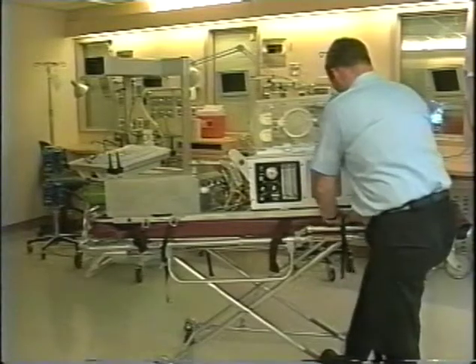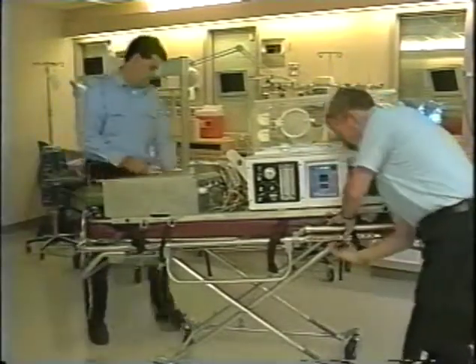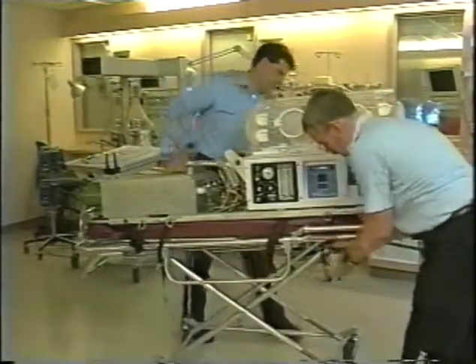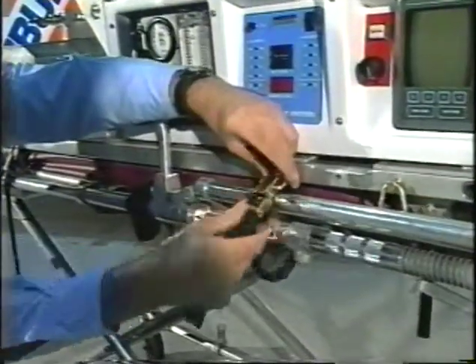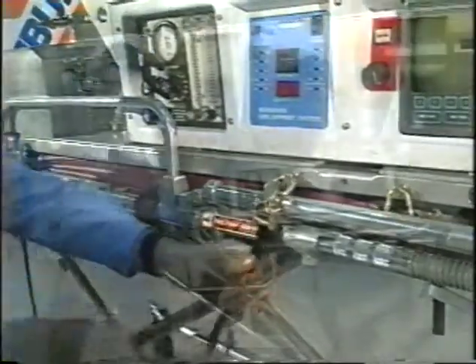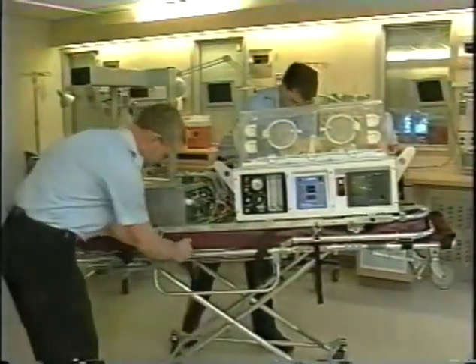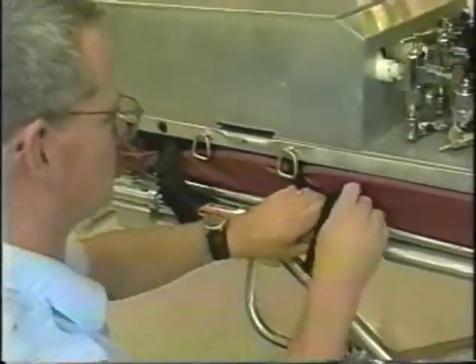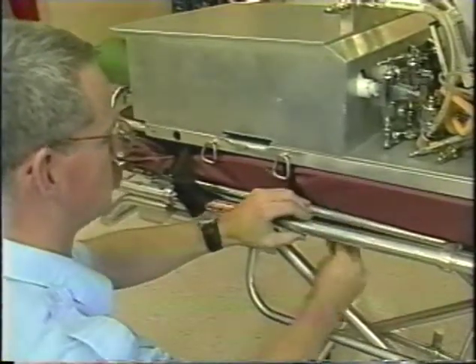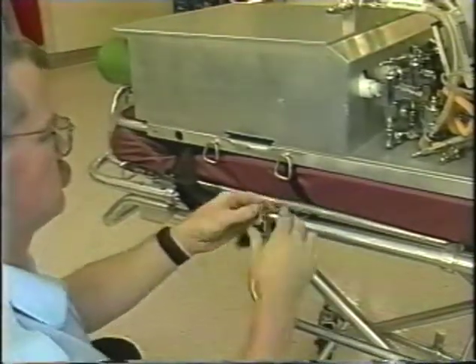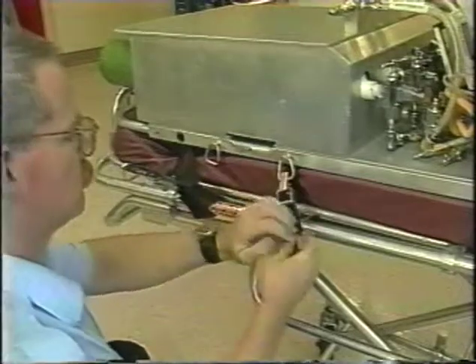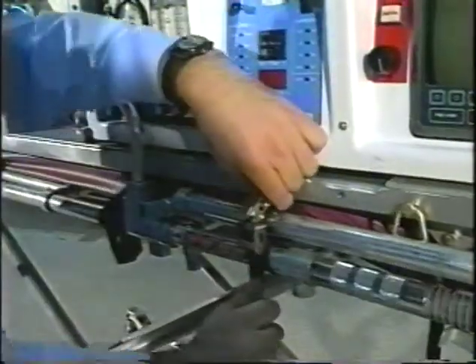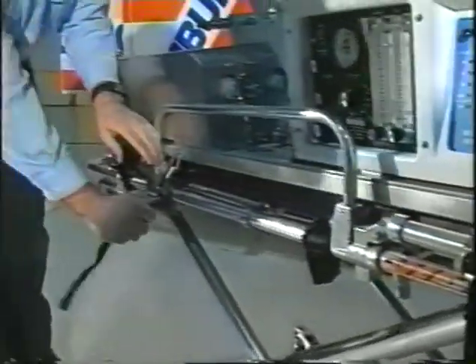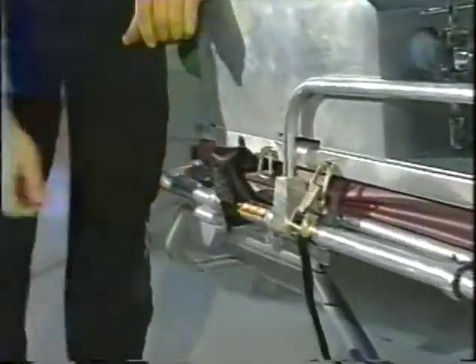Begin to secure the incubator deck to the stretcher by looping each of the 4 safety straps through the main stretcher frame. The close quarters associated with the foot end mechanics of the 35A stretcher will necessitate putting the strap around the main stretcher frame forward of the shock position mechanism. Raise the side rails and clip each of the 4 hook and D-ring combinations together. Make sure the straps are tightened evenly to avoid pulling the adapter deck down on one side.